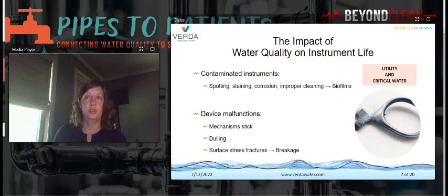Severe corrosion could result in surface stress fractures. Corrosion of a surgical instrument because of salt or other water deposits could result in breakage of the device inside the patient when stress is applied to the device.